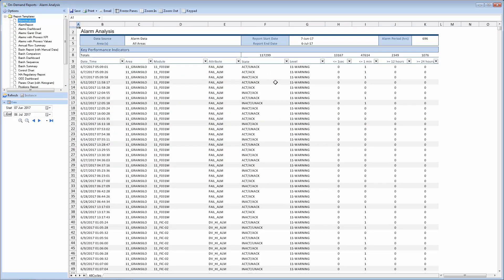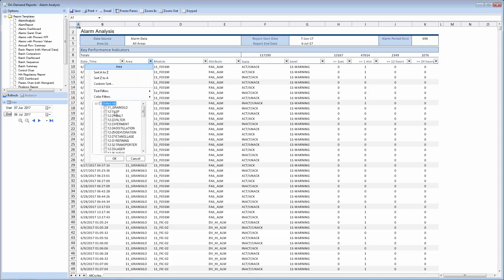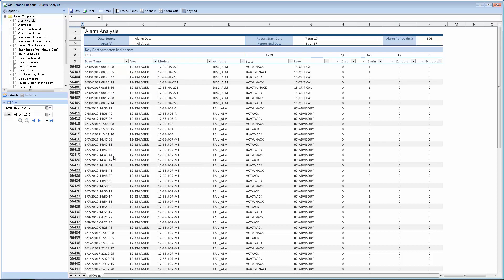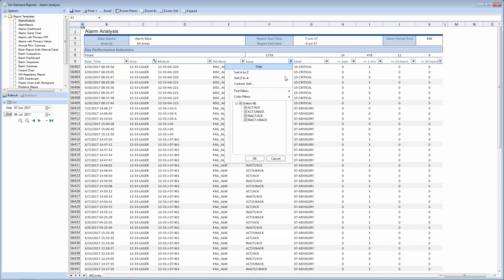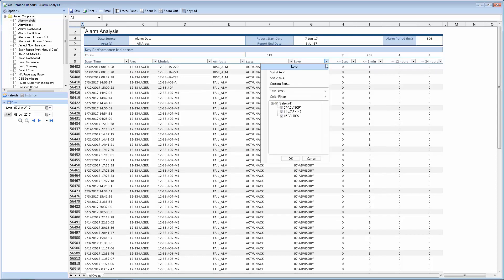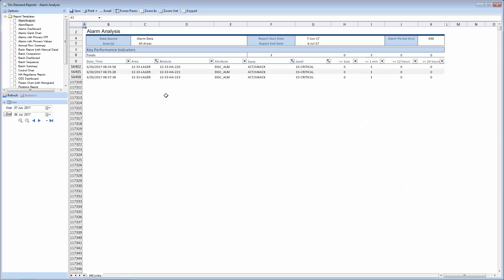An alarm analysis report is also provided that displays every alarm message logged by the system. Filter options allow drilling down into the data based on very specific criteria, such as area, alarm state, and alarm level. Here you can see the start times of the three critical alarms from a particular area over the course of the month. This tool could also be used to view the raw data behind the ISA 18.2 KPIs in an alarm report.